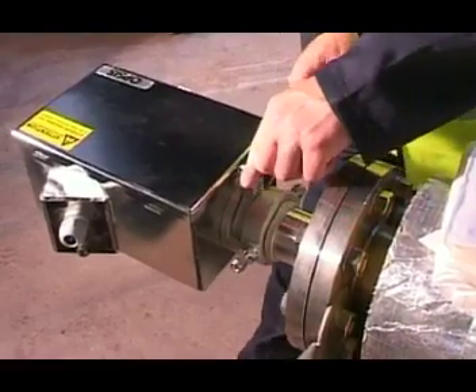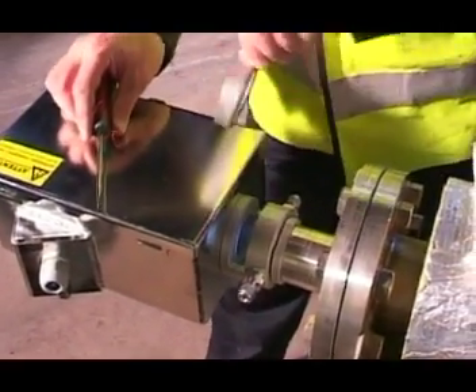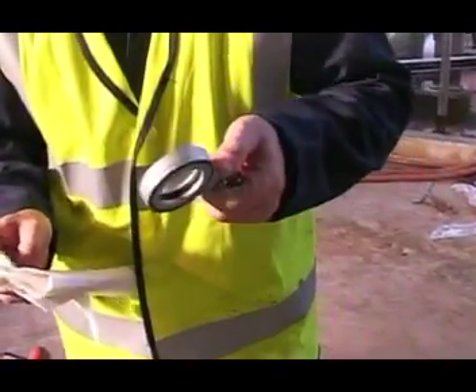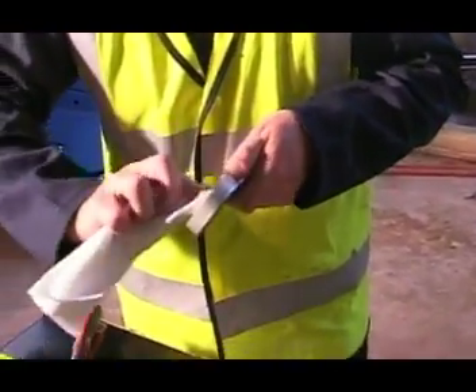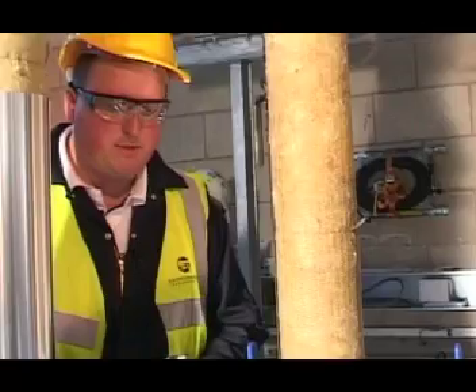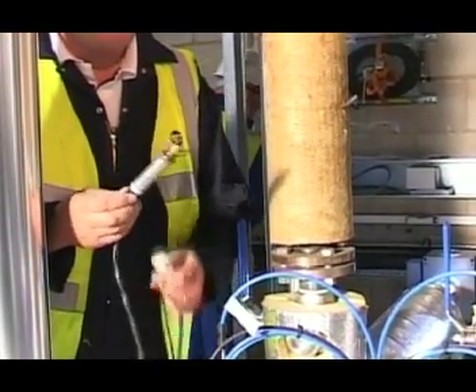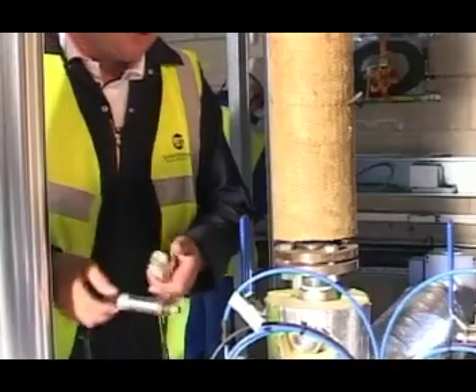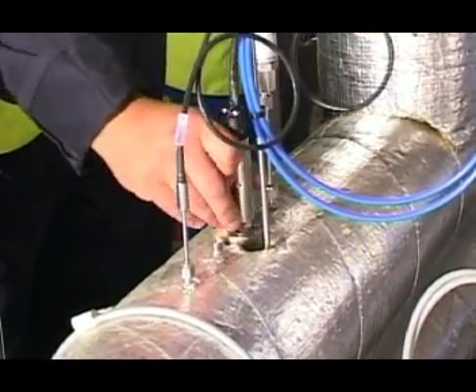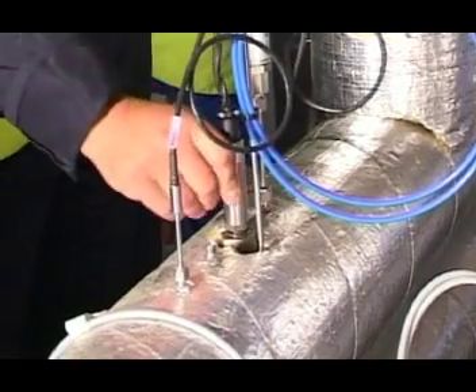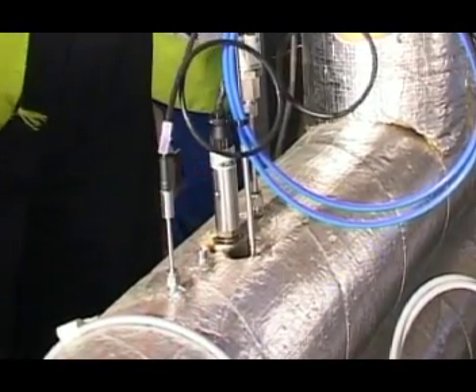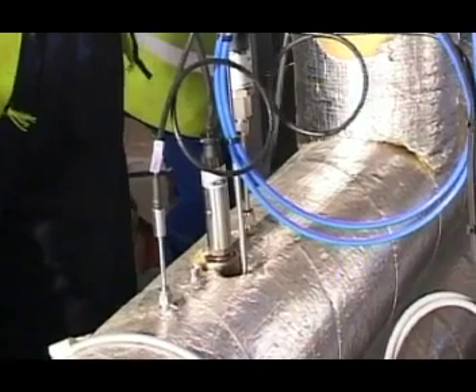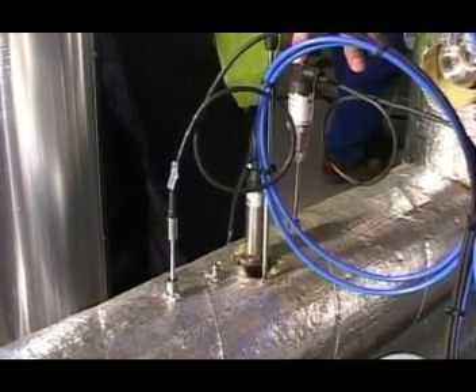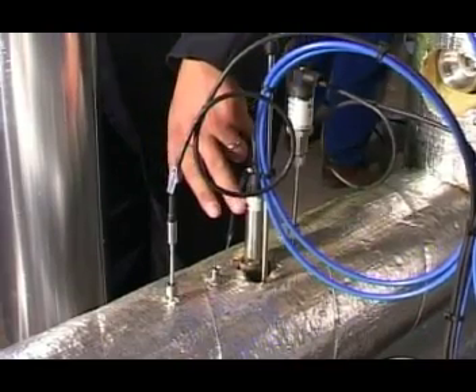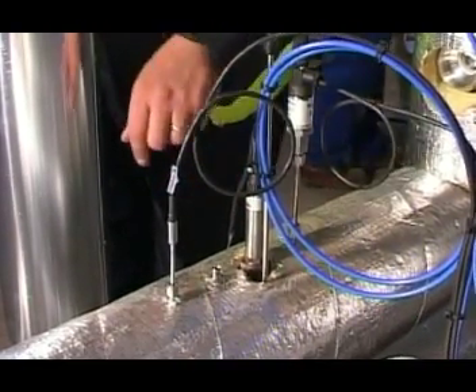Obviously on commissioning we'll set the instrument up, and then every 3 months we'll come back and re-optimise if needed. But apart from all the stack emissions and gases we're monitoring, we're also monitoring pressure, temperature, oxygen. The oxygen is measured using this type of instrument, which is a zirconia cell. The cell is inserted into the measurement bench, and all the signals that come from the zirconia cell are then sent up to the actual small analyzer itself. This sensor measures pressure, this sensor is oxygen, and we also have temperature.